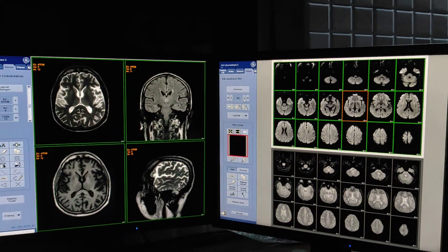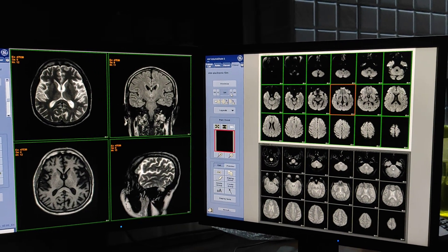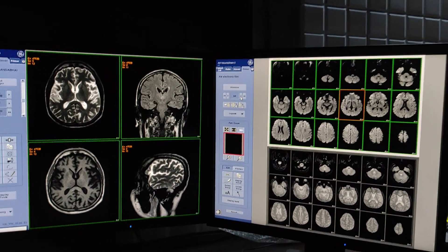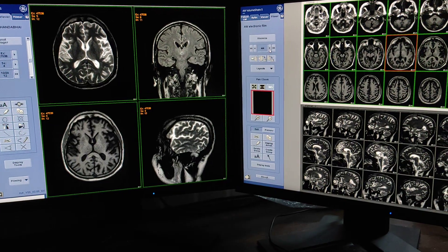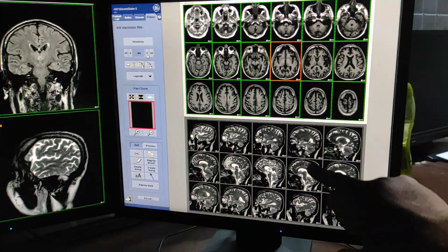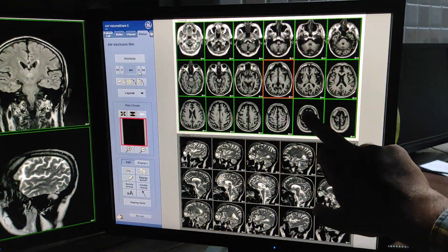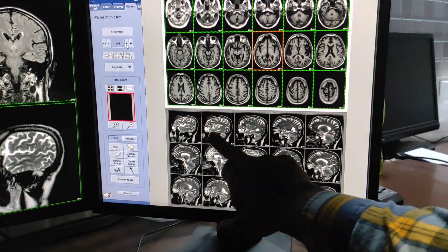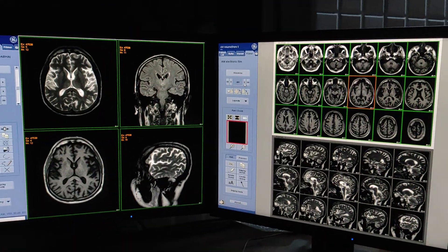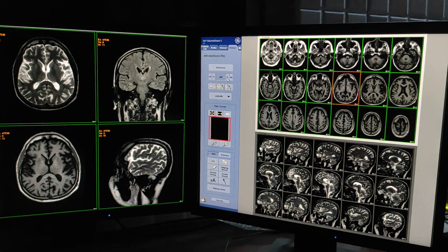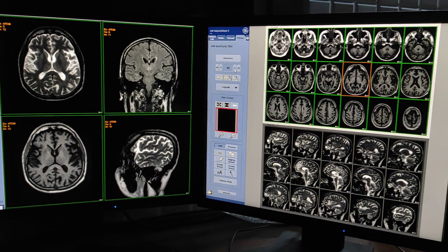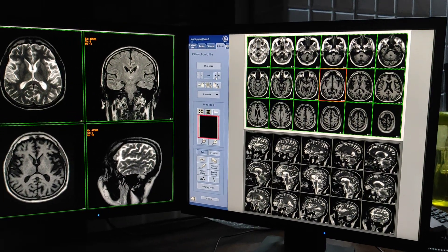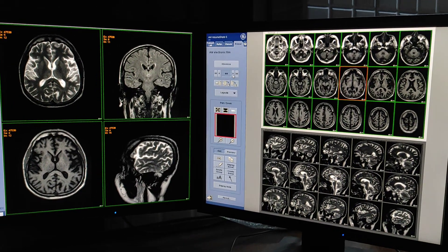This is how you can do the filming of MRI brain. If you are doing contrast, you have to add two more films: one film is for XL big film, and the second film of coronal and sagittal you can give in 18-by-18 format — enter 18 images coronal, adjust the start and end point, and enter from right to left over here. So this is how you can do the filming of MRI brain on ADW 4.6. Hope this video will be informative for you. Please like, share, and subscribe to my channel and press the bell icon for more updates. Thanks for watching.